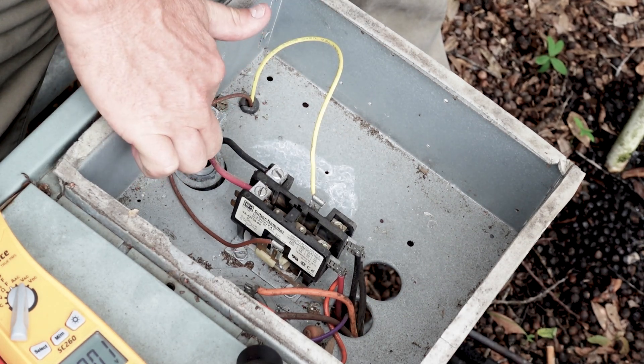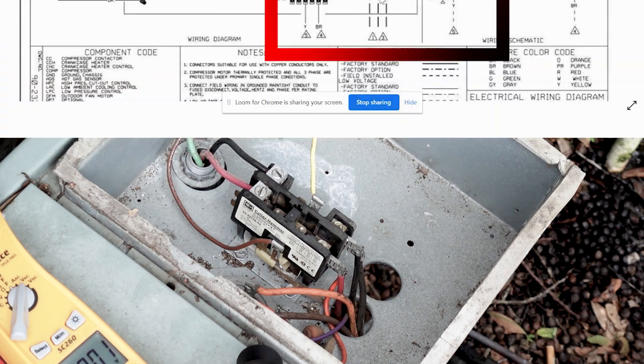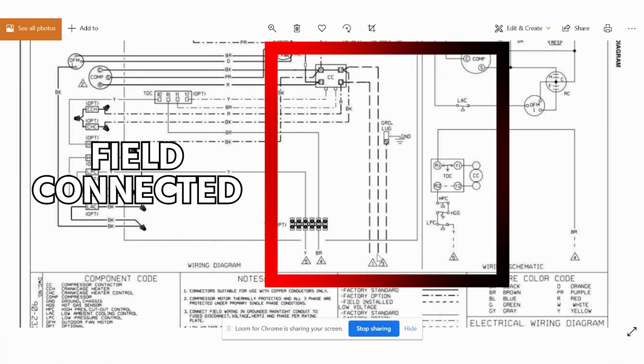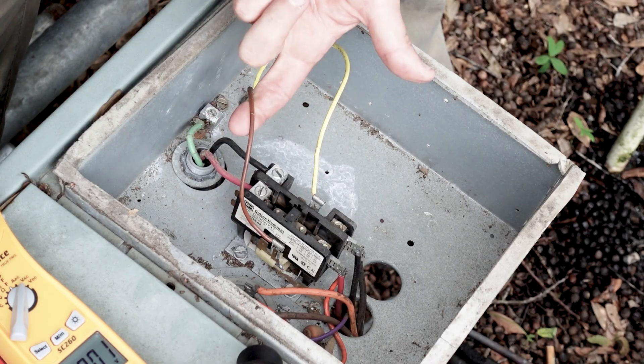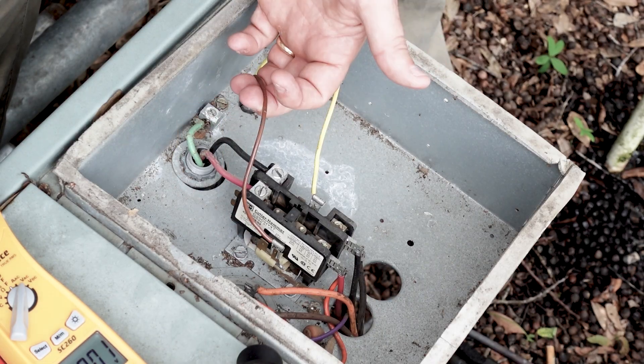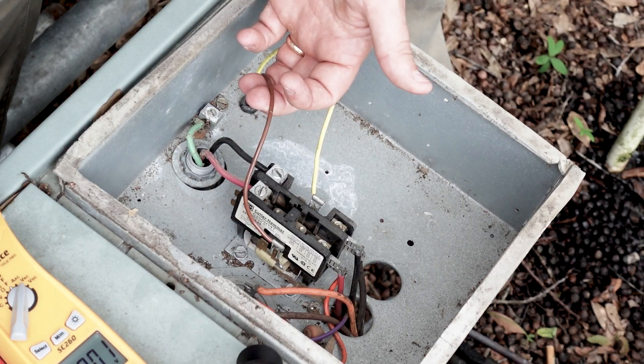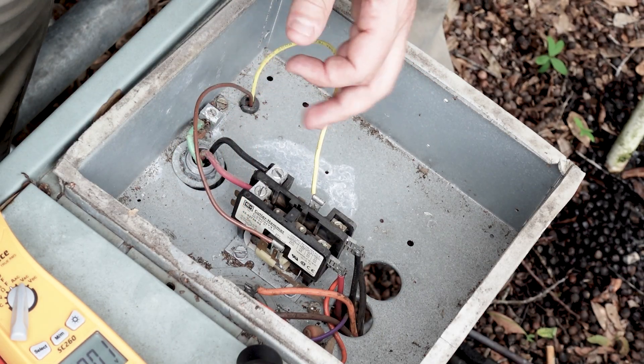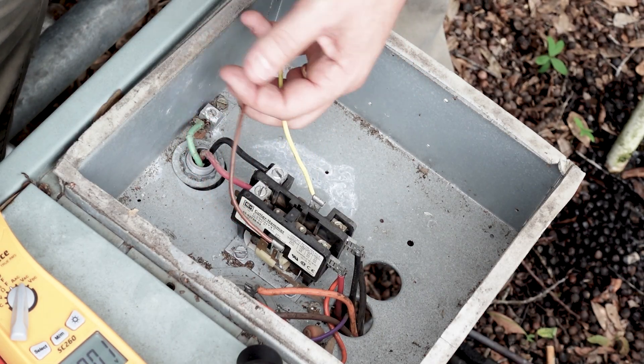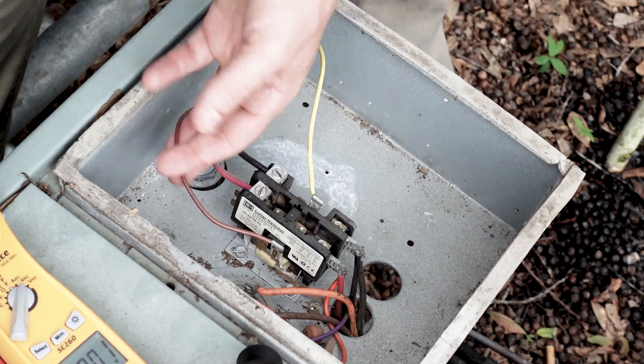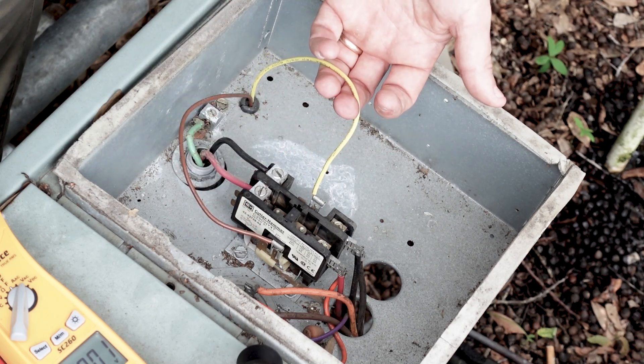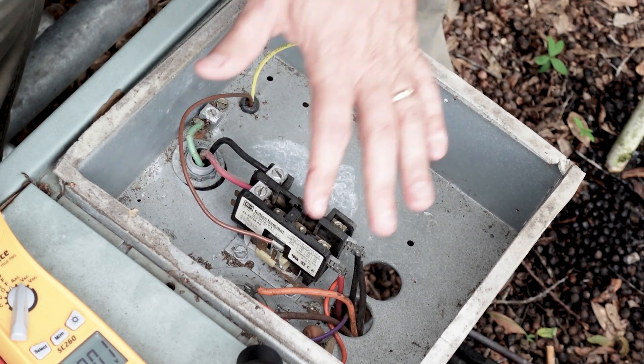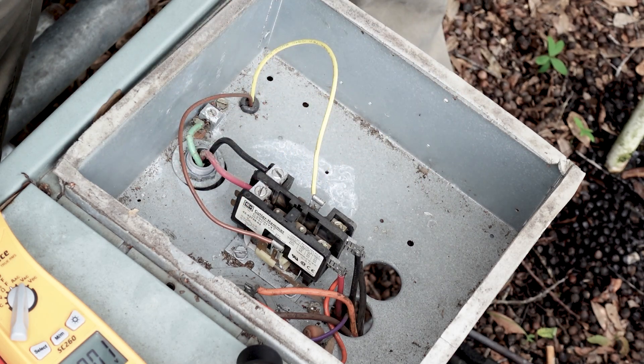So we've got our two high voltage lines coming in from our disconnect. We've got our ground, which is our green. These are what we call field connected wires. And these are going to show as dashes on the diagram. These are our low voltage that come from our thermostat through our air handler.